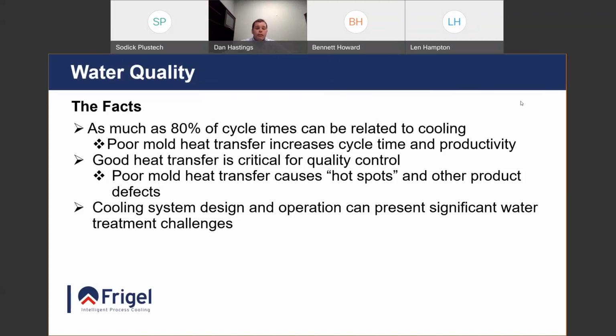Having dirty water plates the inside cooling passages, which reduces heat transfer, but it also can plug Y strainers on molds or temperature control units, or your main system, which is going to affect the flow and pressure you get to your tool.